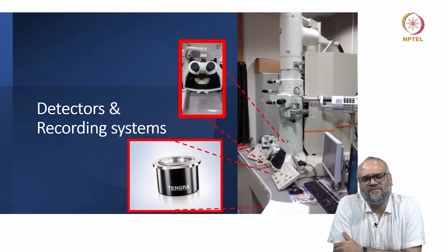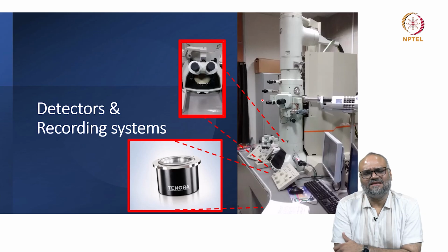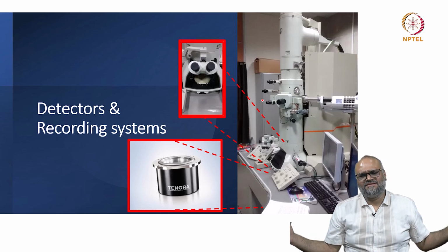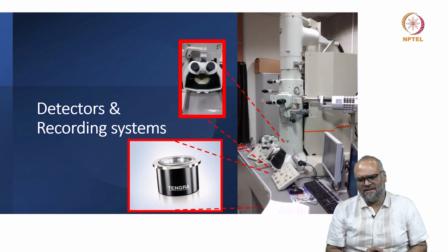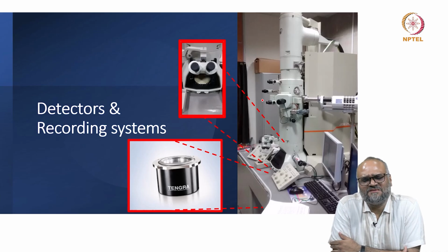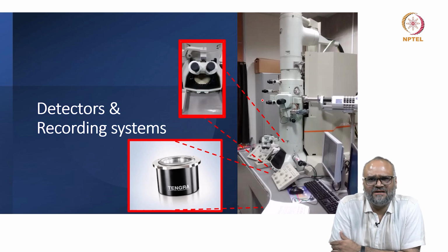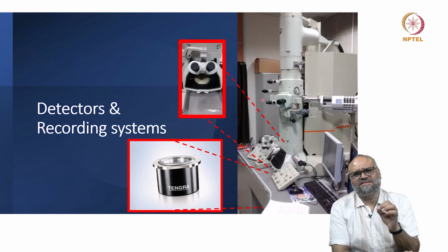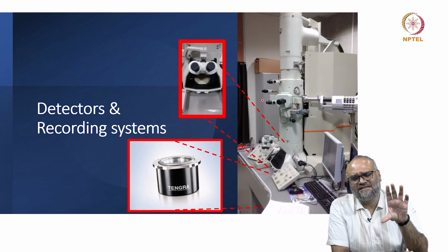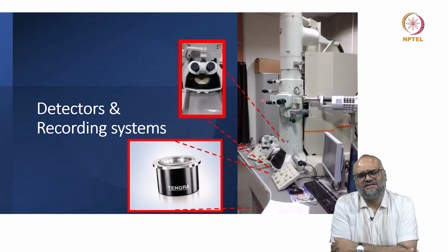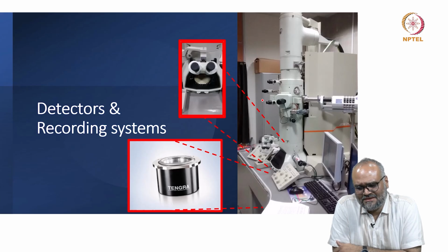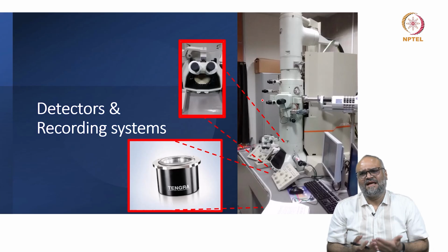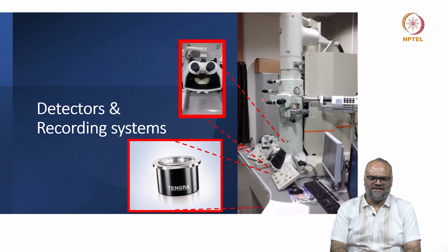Depending on the kind of camera you use, you have something called the dynamic range, that is the maximum range of intensities you can collect, record and save. In fact, the old school image plates had an excellent dynamic range, and these were the best recording media for diffraction patterns. It is extremely important in diffraction patterns because the central spots have the highest intensity, and some of the farther weaker spots do not have such high intensities. So this range of intensities that I can record on a recording medium is the dynamic range.